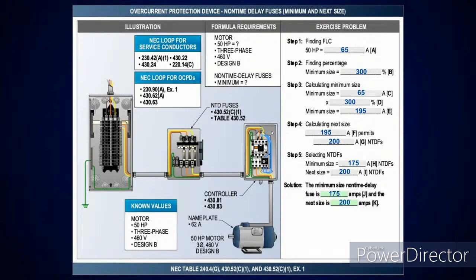Because what it's going to tell you in 430.52(C)(1), the heading's going to say in accordance with table 430.52(C)(1), and it says a protective device that has a rating or setting, listen one more time, not exceeding the value calculated. So that means I can't exceed it. So I have to do what? Drop down to the next standard size. Okay.